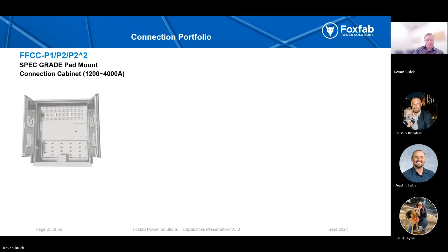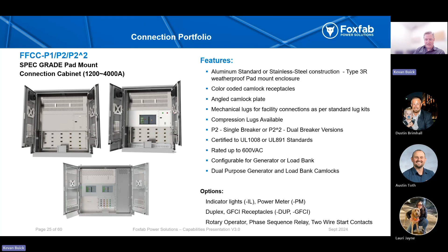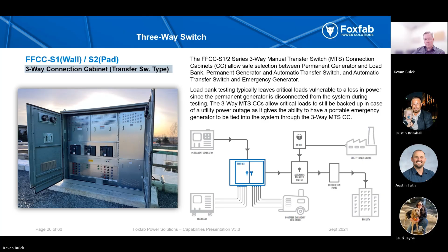And here's the pad mount series of the product line. So much larger, up to 4,000 amp, and you can get those, again, no main device, and you can have them with a range of other devices in it, whether it's single breaker, dual breaker. We can have large transfer switches put in there. We can have a combination of transfer switches and breakers. We also build this unit, as seen in the bottom there, as an automatic transfer switch with cam locks on both the load bank side and the temp gen side. We can build these in service entrance as well. And you'll see a good picture on the next slide here that briefly shows you kind of the interior of one of the units there. I believe that was a 3,000 amp unit with load bank and temp gen connections on it.